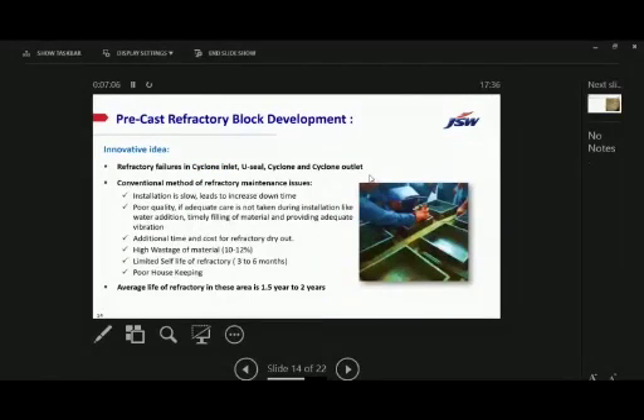Yes, a precast refractory. Actually, the CFBC boilers consist of a high volume of refractories. It is about 1650 metric tons of refractory in a unit. So there are high failures of refractory and a lot of work on the refractories. Our conventional casting of the refractory has some major issues. Its installation is so slow and leads to higher MTTR, and it is quite tough to maintain the quality because it is highly man-oriented work. So adequate care cannot be taken.